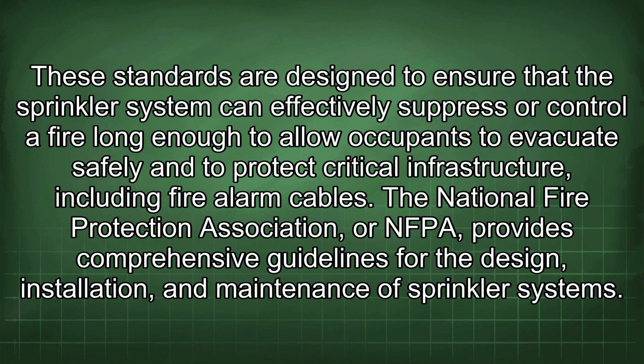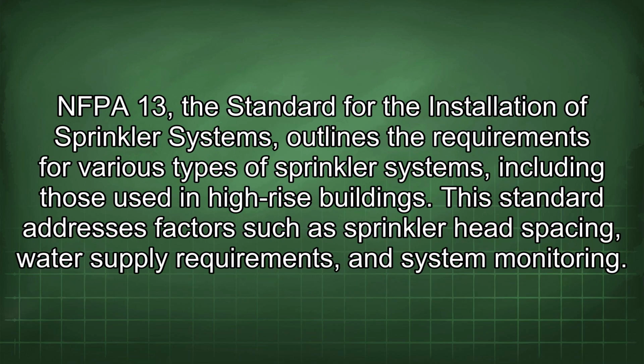The National Fire Protection Association, or NFPA, provides comprehensive guidelines for the design, installation, and maintenance of sprinkler systems. NFPA 13, the standard for the installation of sprinkler systems, outlines the requirements for various types of sprinkler systems, including those used in high-rise buildings. This standard addresses factors such as sprinkler head spacing, water supply requirements, and system monitoring.